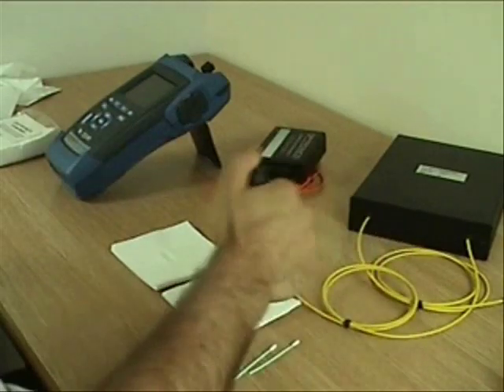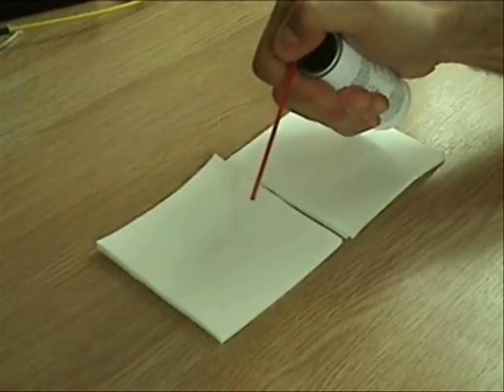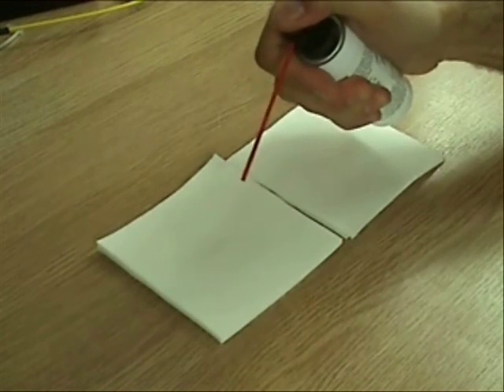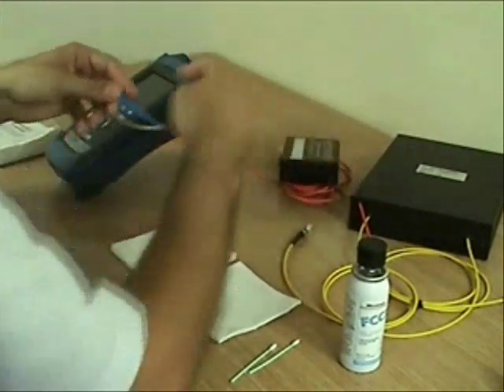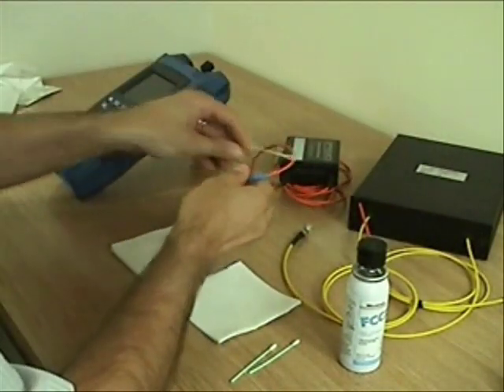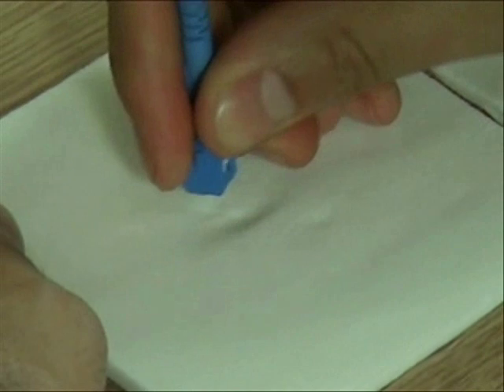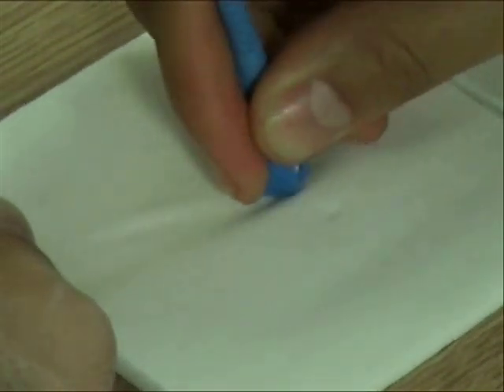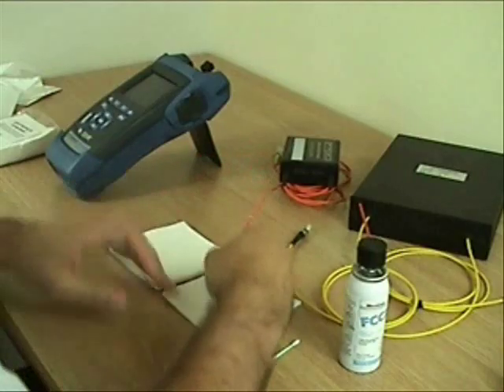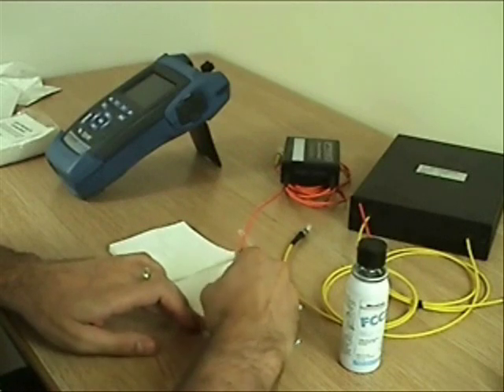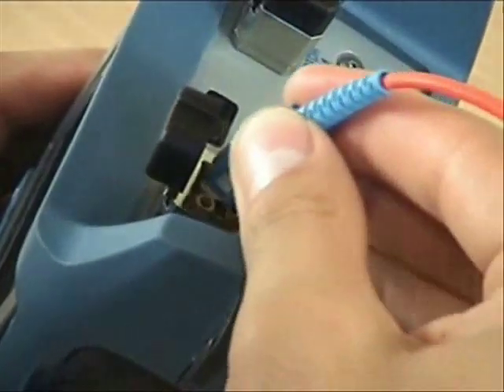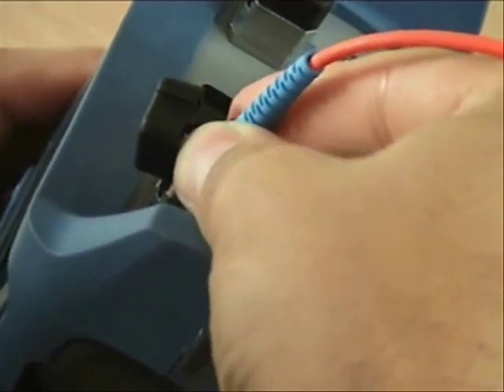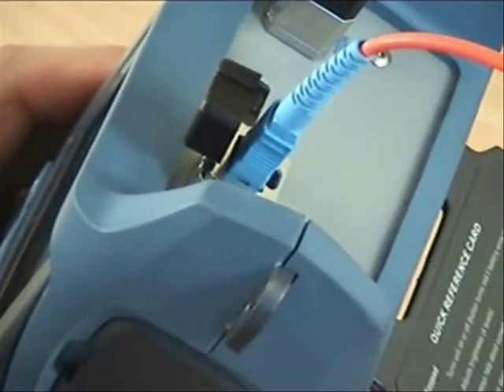Next, spray some cleaning fluid onto one of the piles of lint free cloths. Take one connector from the launch lead, remove the protective cap and wipe through the moist tissue two or three times to remove any dirt. Repeat this process on the dry pile and then connect to the multi-mode port of the OTDR.